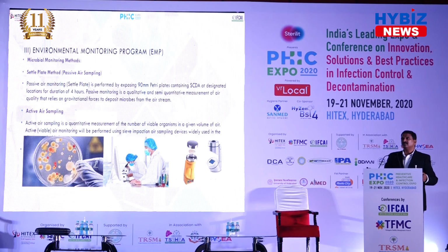Settle plate exposure, also called passive air monitoring, is a qualitative way of monitoring the environment. 90 mm plates are used for monitoring for a 4 hour duration, wherein it is expected that around 1000 liters of air is passing through those plates. However, it is a qualitative way. The first picture shows the plate used for the settle plate method, and after incubation those are the colonies observed on the plate. There are different types of colonies. It may include yeast and molds also.